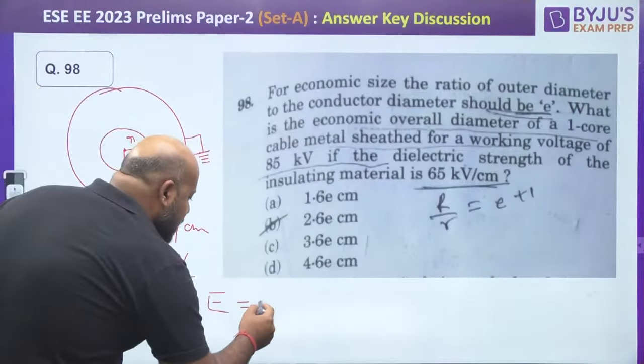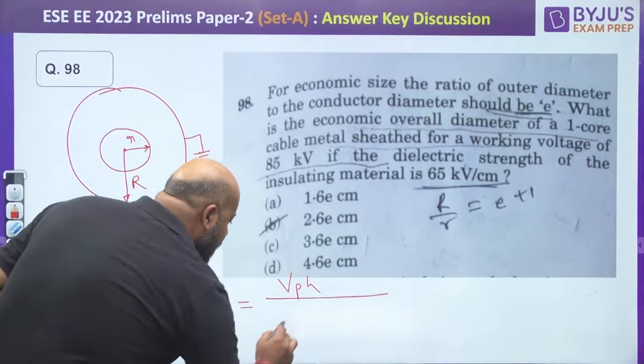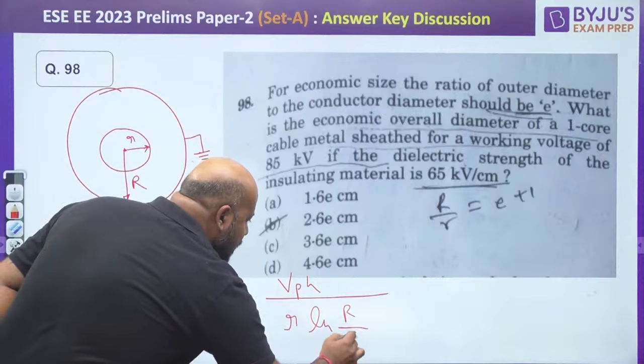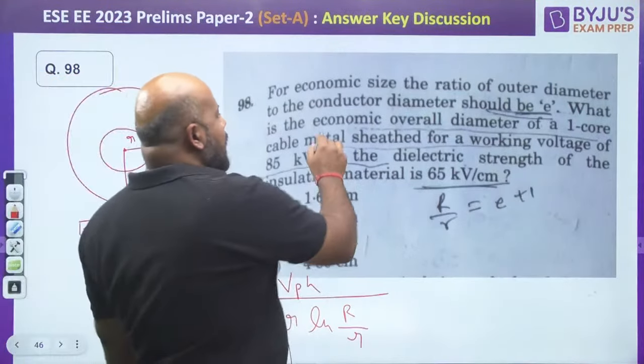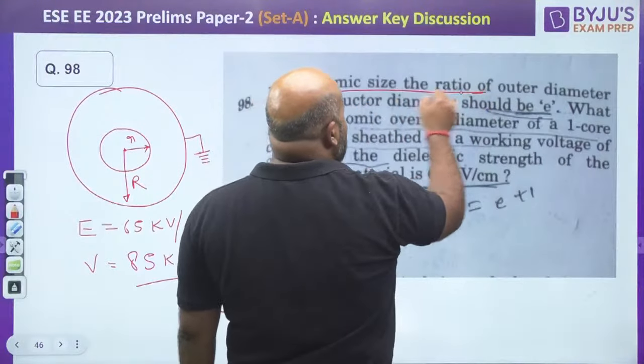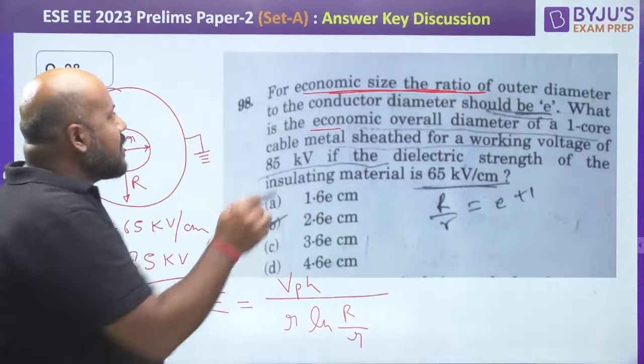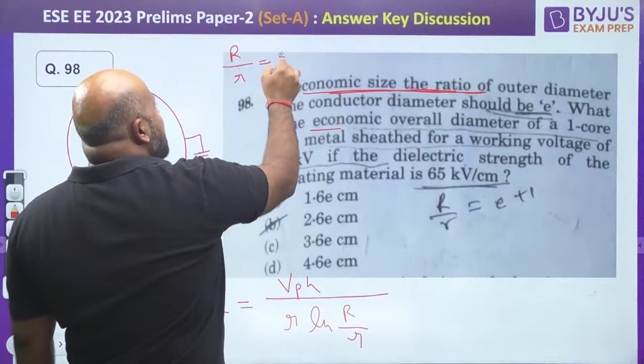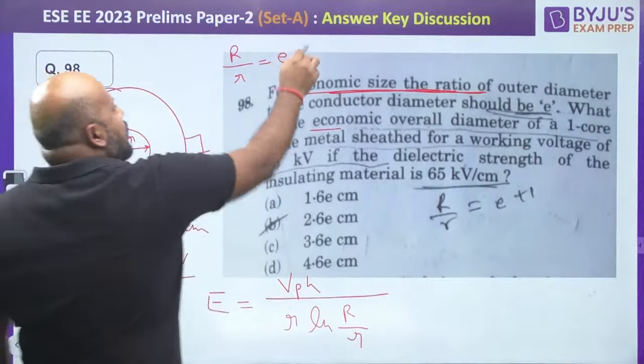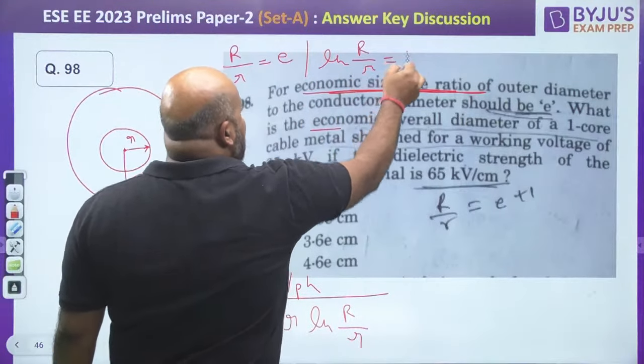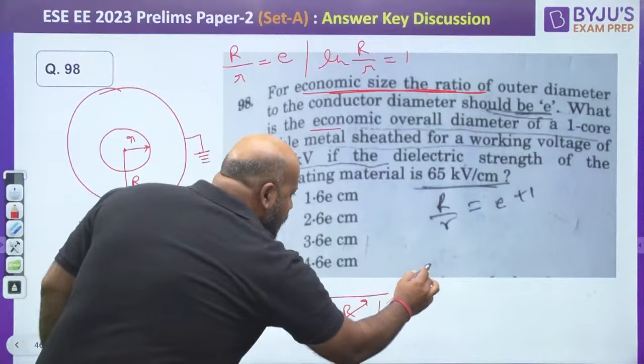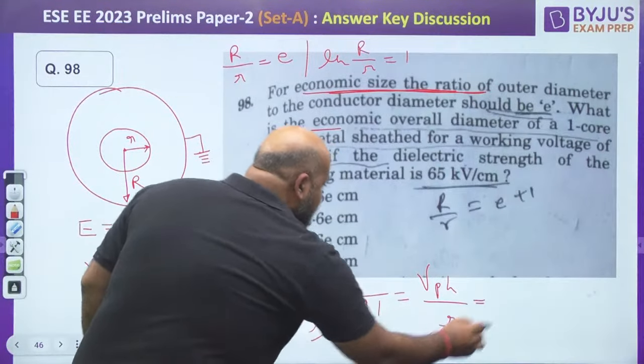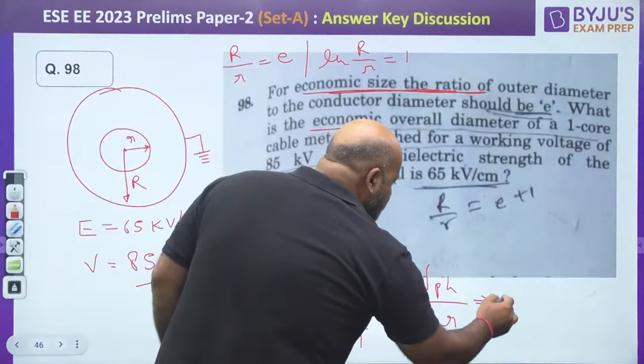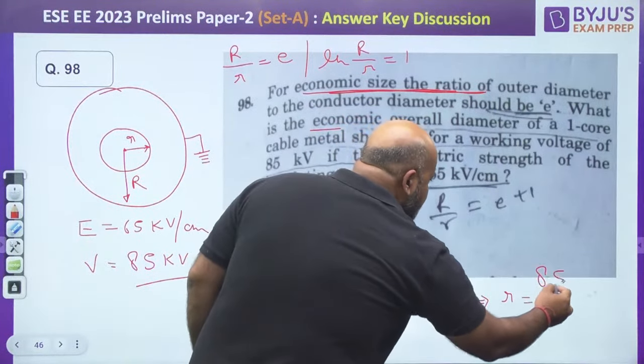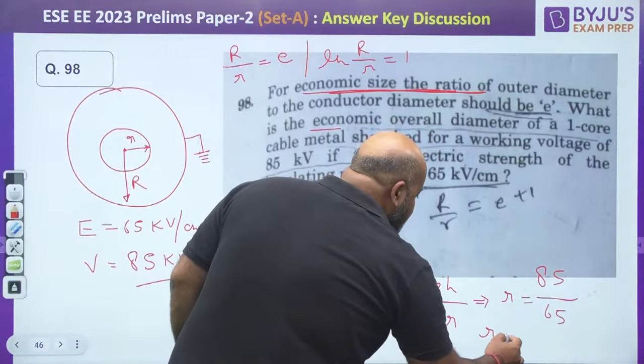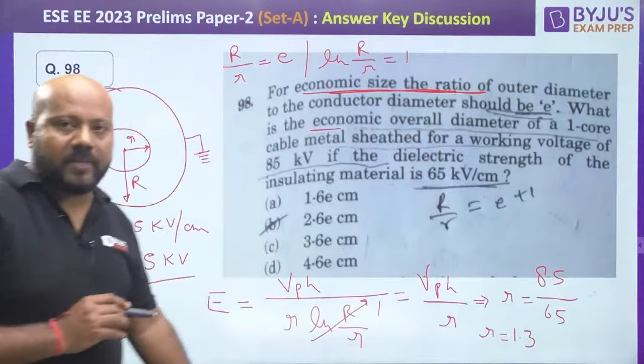You can write it as V phase upon r, ln(R/r). But for the condition of overall economic size of the core, you have the condition that the R/r ratio should equal E. So if R/r is E, then ln(R/r) becomes 1. So this simplifies to V phase upon small r equals E, where voltage is 85 and E is 65. Solving this, you get r somewhere around 1.3 centimeters.